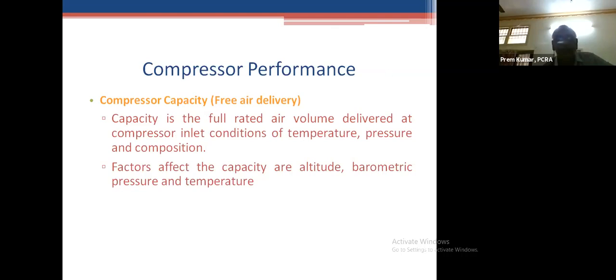So here we should be very careful in sizing the compressor. One company, an R&D company, for a mere usage of 100 CFM, had gone for 750 CFM, and most of the time it was running in unloaded condition. They could have gone with 200 CFM, or at least 100 CFM should be affordable. Or, in case future equipment is coming, the consultant has recommended one 200 CFM unit initially, which can be supplemented when they go in for expansion.